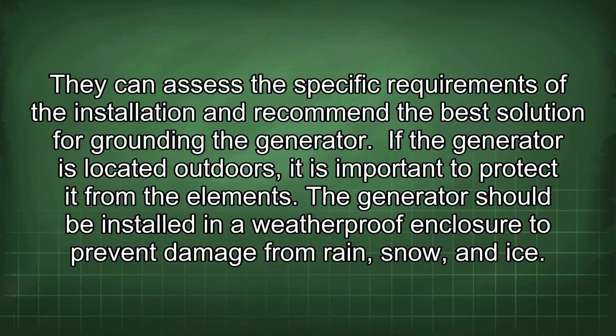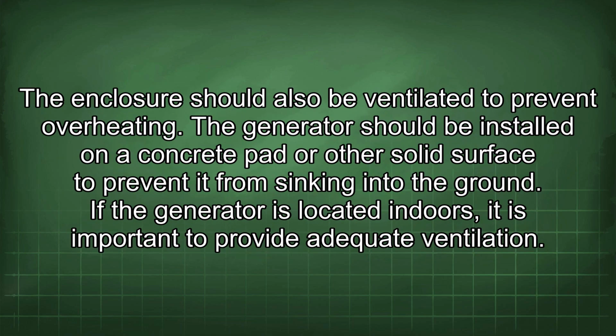If the generator is located outdoors, it is important to protect it from the elements. The generator should be installed in a weatherproof enclosure to prevent damage from rain, snow, and ice. The enclosure should also be ventilated to prevent overheating.